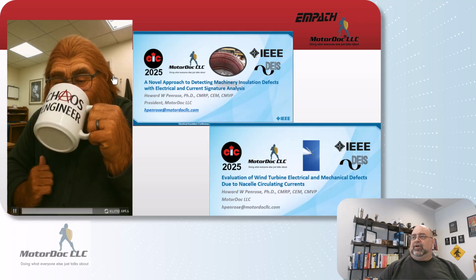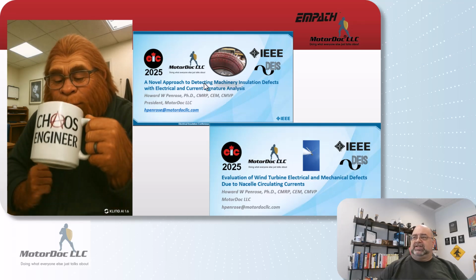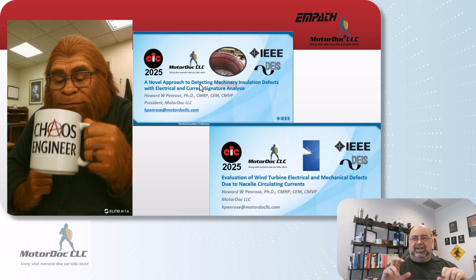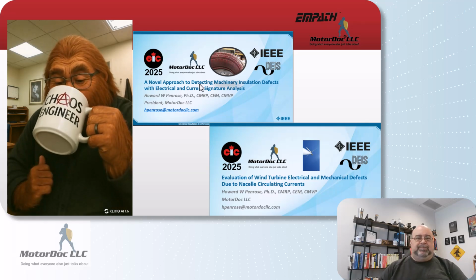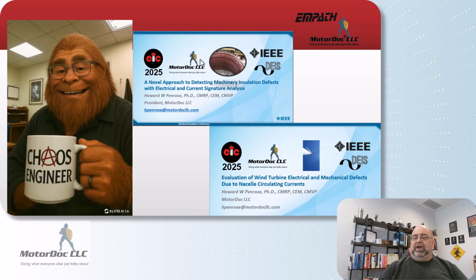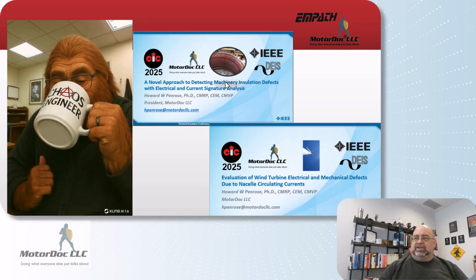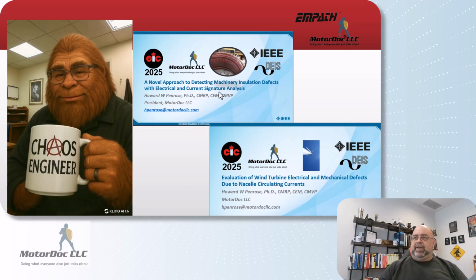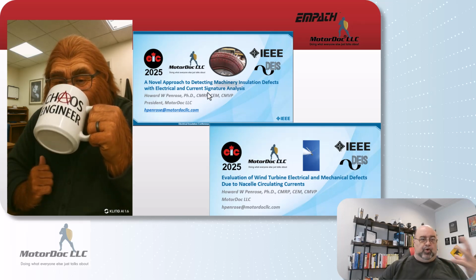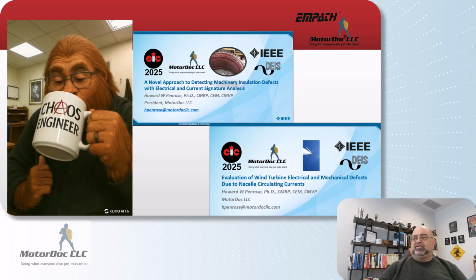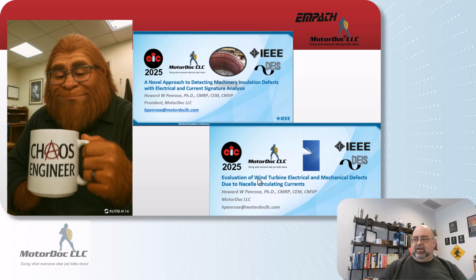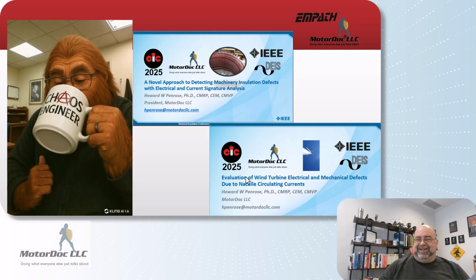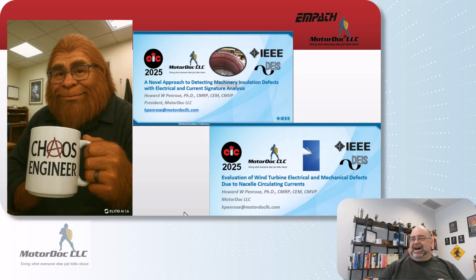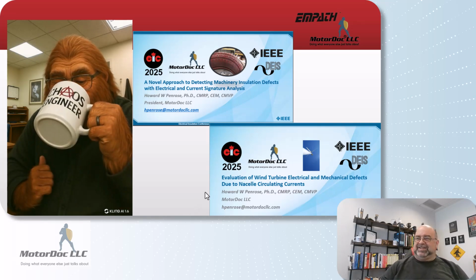So one of the things that had been brought up was that they were developing this method for determining insulation breakdown. Well, that's probably because I hadn't published the paper publicly at that point. This was 1 month ago. The paper I gave at IEEE, because of the work that we've done for several years on this particular issue. This one here has to do with circulating currents. There's another company trying to take credit for that. I tell you, I've been just absolutely amazed. But in any case, that's why you're going to hear some of the true history of what's going on with these systems.